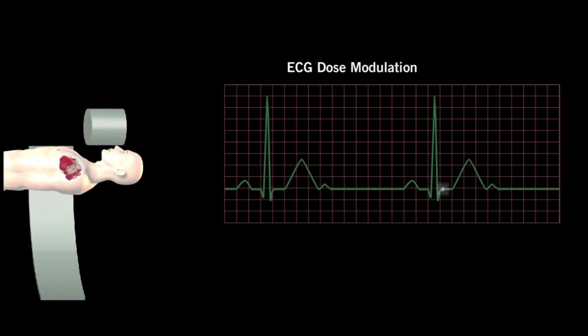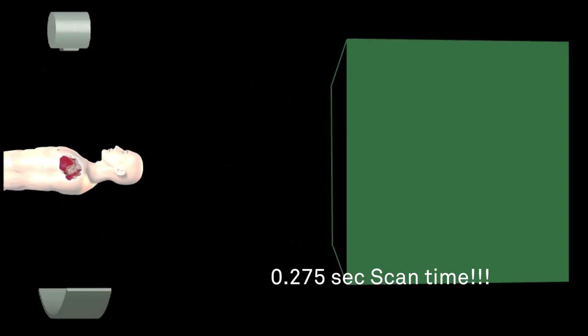And here's a nice diagram that basically shows you how fast a 320 slice cardiac CT works. I'll play this. So this is, again, the ECG tracing, and you're going to tell the CT scanner that you want to take a picture here. This is the patient, obviously the heart. Patient's arm would be at the top. And you run the machine, ECG goes, machine spins, boop, picture taken, machine stops, works for a few seconds, and then there you go, got your picture. So that's a fraction of a second. That's how quick it was.